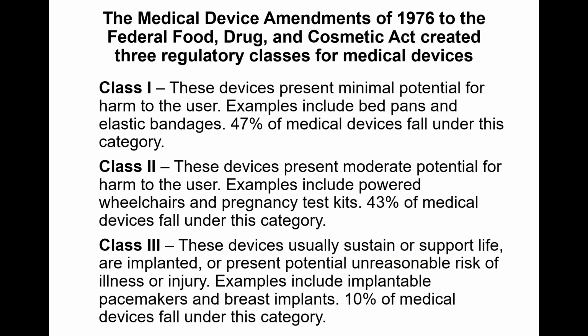So with that, I now want to introduce you to a summary of what we've gone through thus far: the FDA regulatory requirements, namely the Medical Device Amendments, 21 CFR, and a 3-tiered risk-based classification of medical devices. If your product is intended to treat, cure, diagnose, prevent, or detect disease, and it doesn't achieve its primary mechanism of interaction through chemical interaction, then it's going to be regulated as a medical device. But that doesn't dictate which class of medical device until you can specify the intended use.